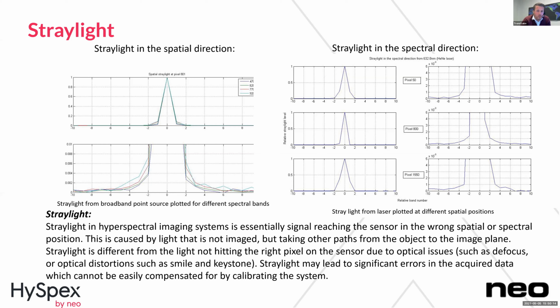The way we do it, both spectrally and spatially, is by having very narrow spectral sources and point sources, and we look at the energy a few pixels away from those, and we scan it across the whole field of view to measure the stray light. Basically, stray light is light that's hitting the detector that's not supposed to be there. It can be scattering from the optics, it can be reflections from the mechanics inside, and so on.